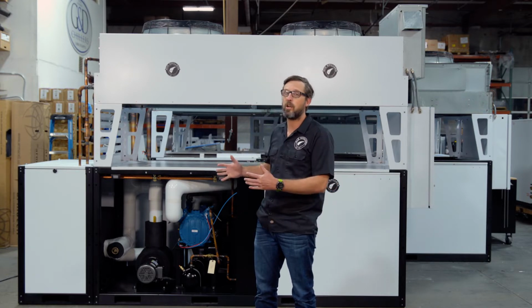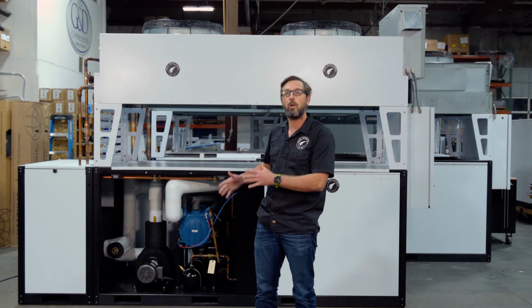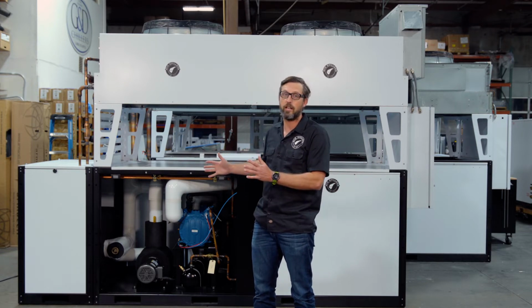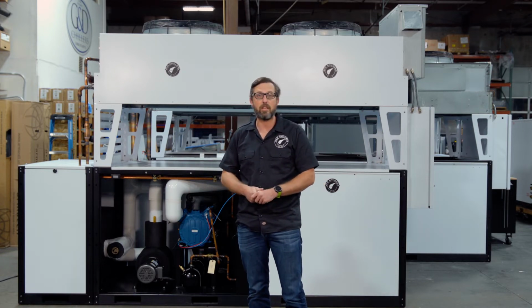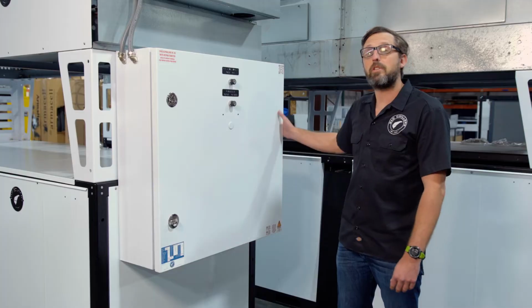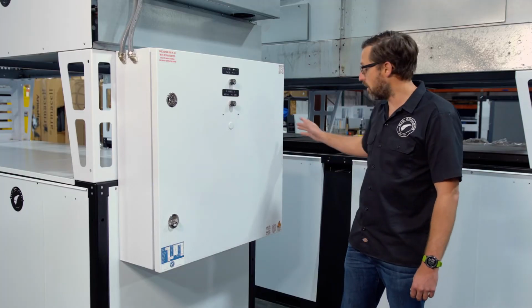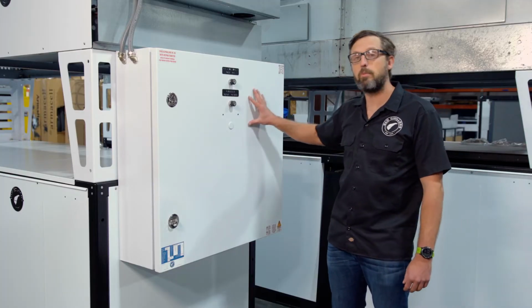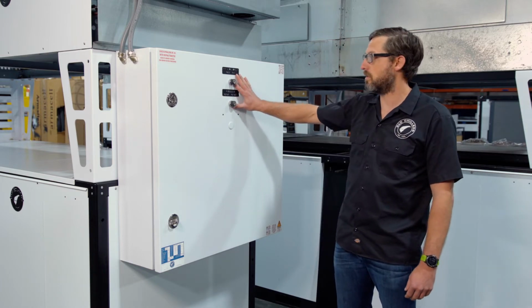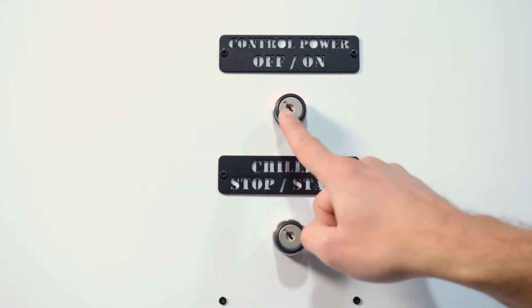The first thing we're going to want to ensure is that the chiller's on a level pad with adequate clearances on all sides. Once we've ensured that that's the case, we're going to head over to the control panel. Alright, so now that we've ensured that the installation's looking good and we've got power running to the system, we're going to come to the control panel and look at these two door switches. We want to make sure that they are both in the off position.